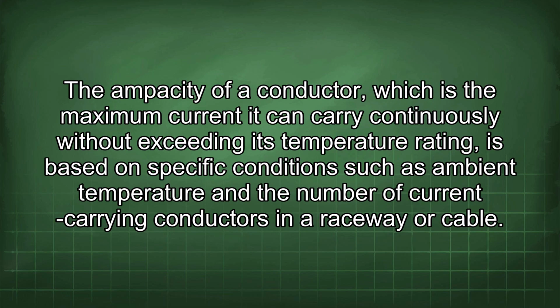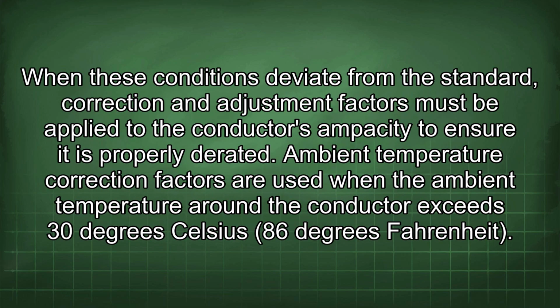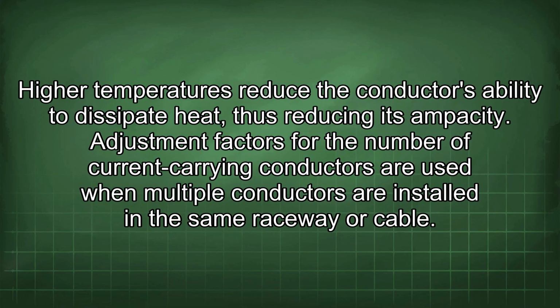The ampacity of a conductor, which is the maximum current it can carry continuously without exceeding its temperature rating, is based on specific conditions such as ambient temperature and the number of current-carrying conductors in a raceway or cable. When these conditions deviate from the standard, correction and adjustment factors must be applied to the conductor's ampacity to ensure it is properly derated. Ambient temperature correction factors are used when the ambient temperature around the conductor exceeds 30 degrees Celsius (86 degrees Fahrenheit). Higher temperatures reduce the conductor's ability to dissipate heat, thus reducing its ampacity.